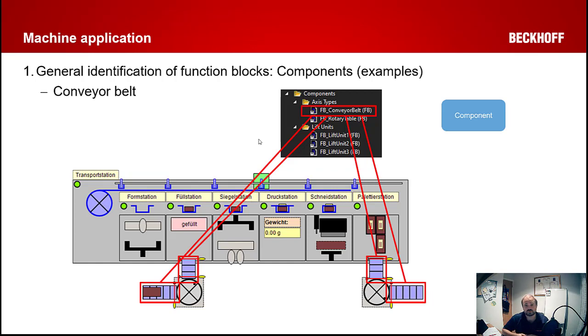Going one level further down, the same thing is true of the equipment modules and the components. The conveyor belt, for example, for the filling station or for the palletization station. The class of the filling station doesn't care how the conveyor belt works. All it wants to be able to do is tell the conveyor belt to move or not move so they can bring product into the fill station. All of the code that makes the conveyor belt actually run is all abstracted away and encapsulated inside the component that is the conveyor belt. How it makes a conveyor belt move using velocity, for example, how it maintains its state machine, is all hidden inside that class. The equipment module doesn't care how it operates, it just wants to be able to use it.